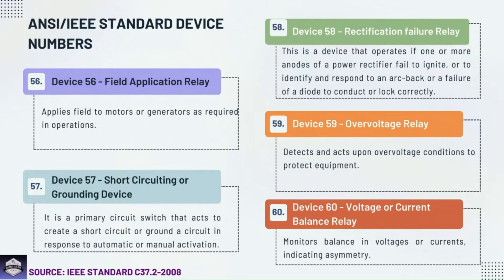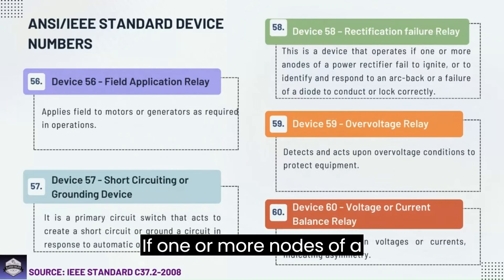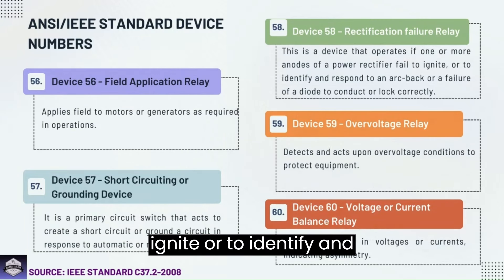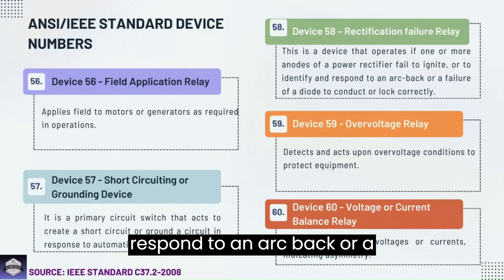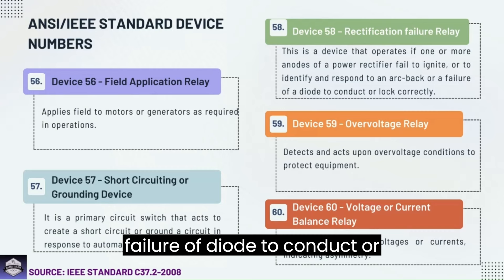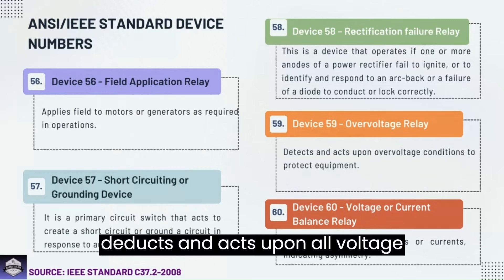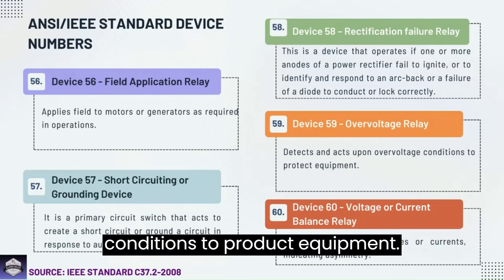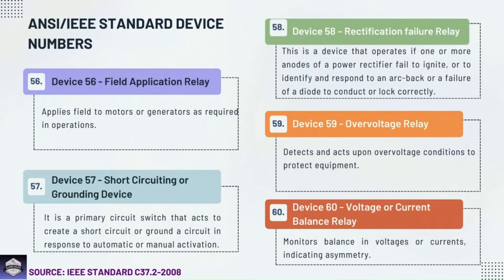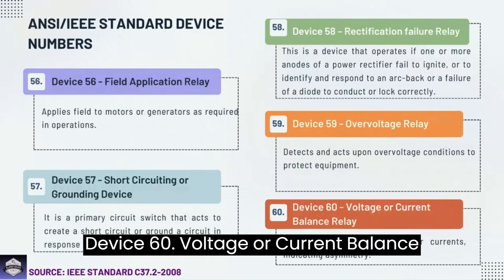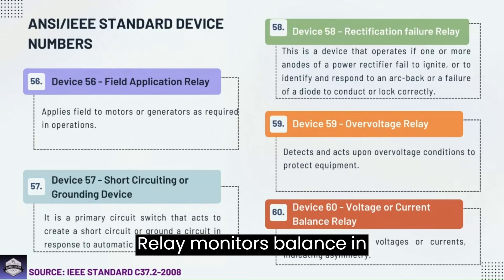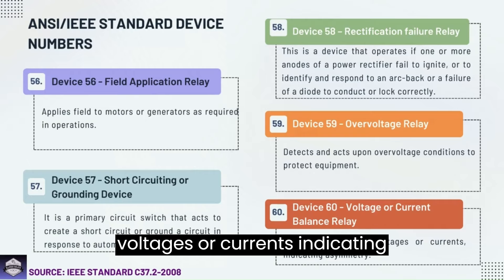Device 58: Rectifier failure relay — a device that operates if one or more anodes of a power rectifier fail to ignite, or to identify and respond to an arc-back or a failure of a diode to conduct or block correctly. Device 59: Overvoltage relay — detects and acts upon overvoltage conditions to protect equipment. Device 60: Voltage or current balance relay — monitors balancing voltages or currents, indicating asymmetry.